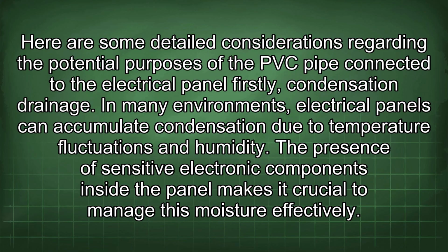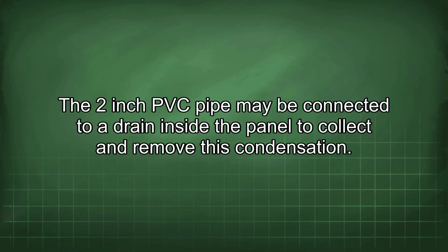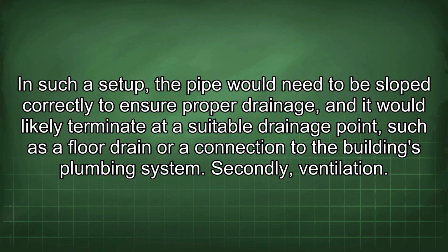Firstly, condensation drainage. In many environments, electrical panels can accumulate condensation due to temperature fluctuations and humidity. The presence of sensitive electronic components inside the panel makes it crucial to manage this moisture effectively. A 2-inch PVC pipe may be connected to a drain inside the panel to collect and remove this condensation. In such a setup, the pipe would need to be sloped correctly to ensure proper drainage, and it would likely terminate at a suitable drainage point, such as a floor drain or a connection to the building's plumbing system.